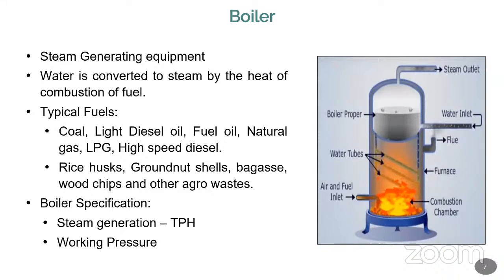This is again similar to the voltage in an electrical system. So you need to produce the steam at the required pressure. Then only will the steam flow from your boiler to the end of the process. Sometimes it may be 1 or even 2 kilometers from your boiler. If you go to leather industries or even modern rice mills, the boiler is very far away from the dryer area, around 0.5 kilometers. So you need a proper pressure to flow the steam from your boiler.